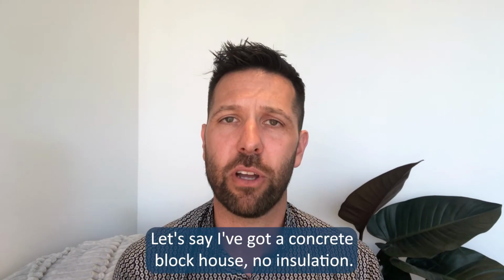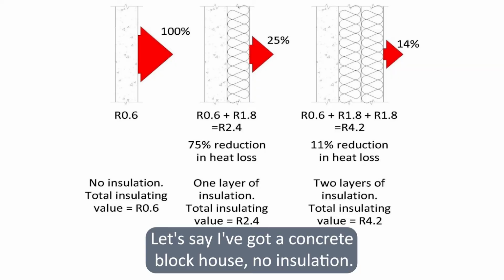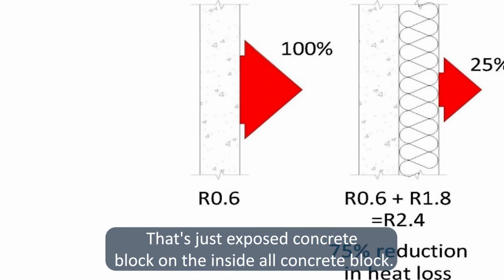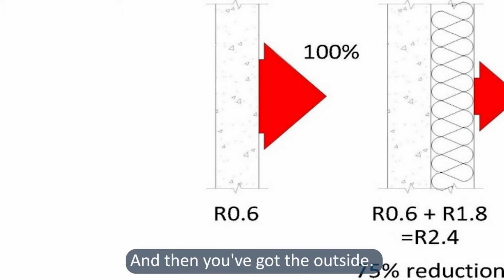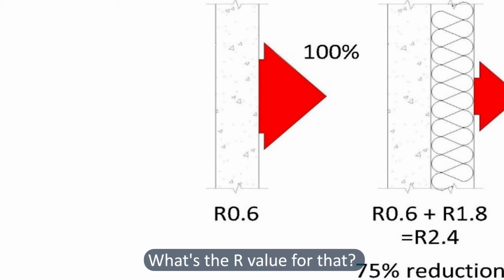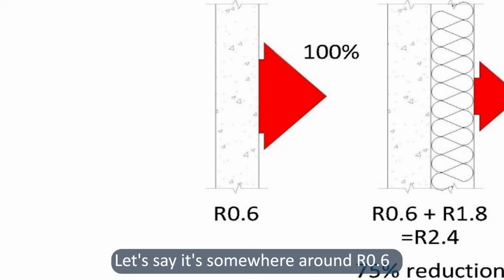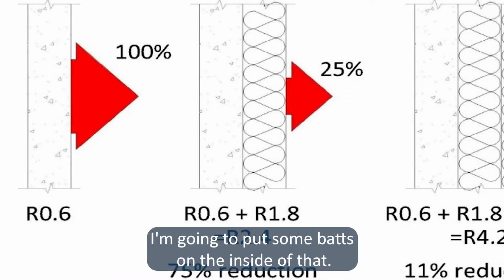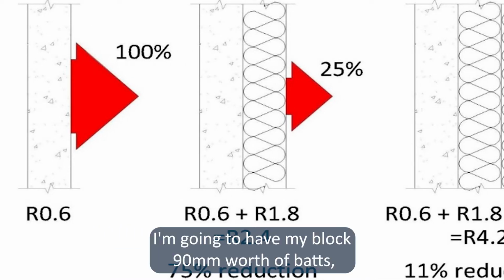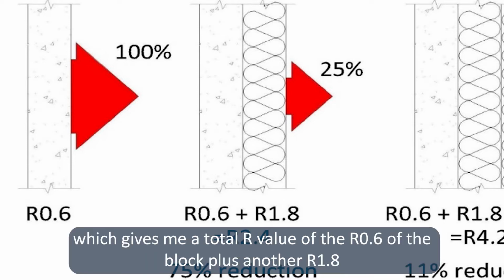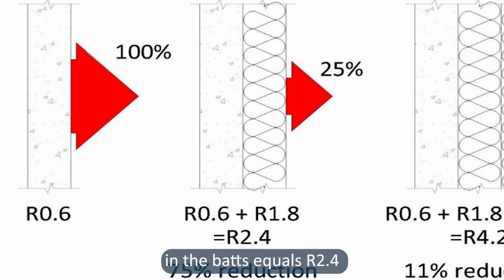Let's say I've got a concrete block house, no insulation. It's just exposed concrete block on the inside, all concrete block, and then you've got the outside. What's the R value for that? Let's say it's somewhere around 0.6. I'm going to put some batts on the inside of that. I'm going to have my block, 90mm worth of batts, which gives me a total R value of the 0.6 of the block plus another 1.8 in the batts, so 2.4.